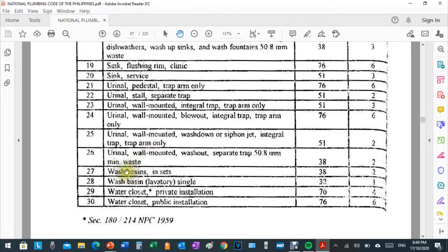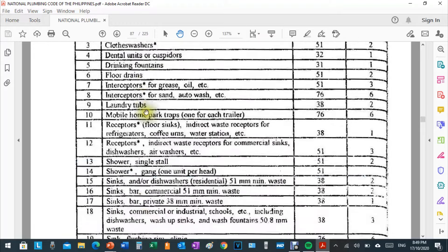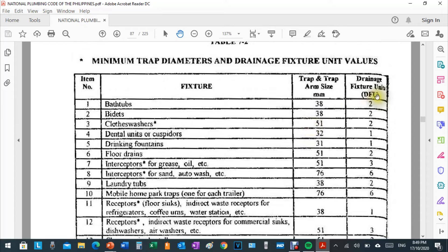For water closets, the minimum trap arm is 76 millimeters or 3 inches, with a drainage fixture unit of 4 for private installation. For public installation, the same minimum trap arm diameter applies but the drainage fixture unit is 6. Wash basins or lavatories have 32 millimeters and one drainage fixture unit. There are many fixtures listed with their equivalent trap arm diameter and drainage fixture unit values.